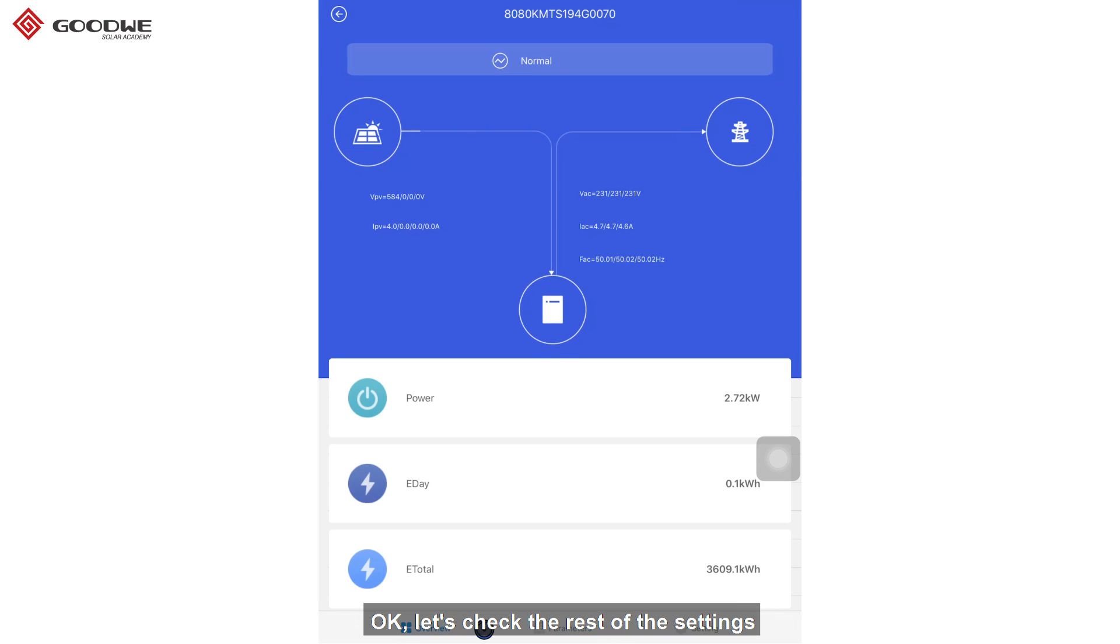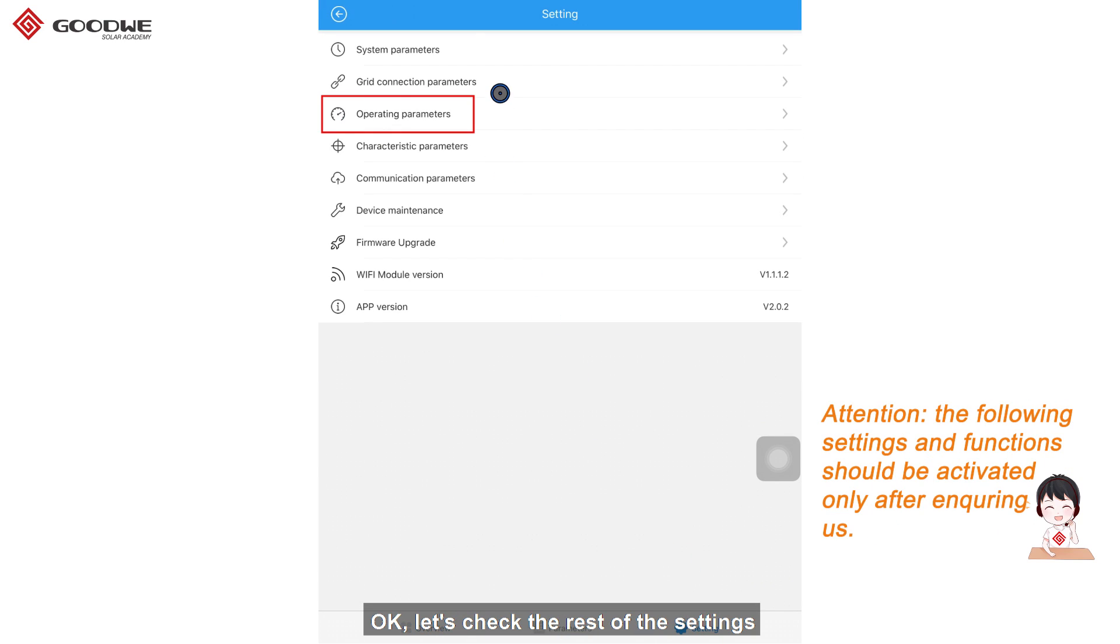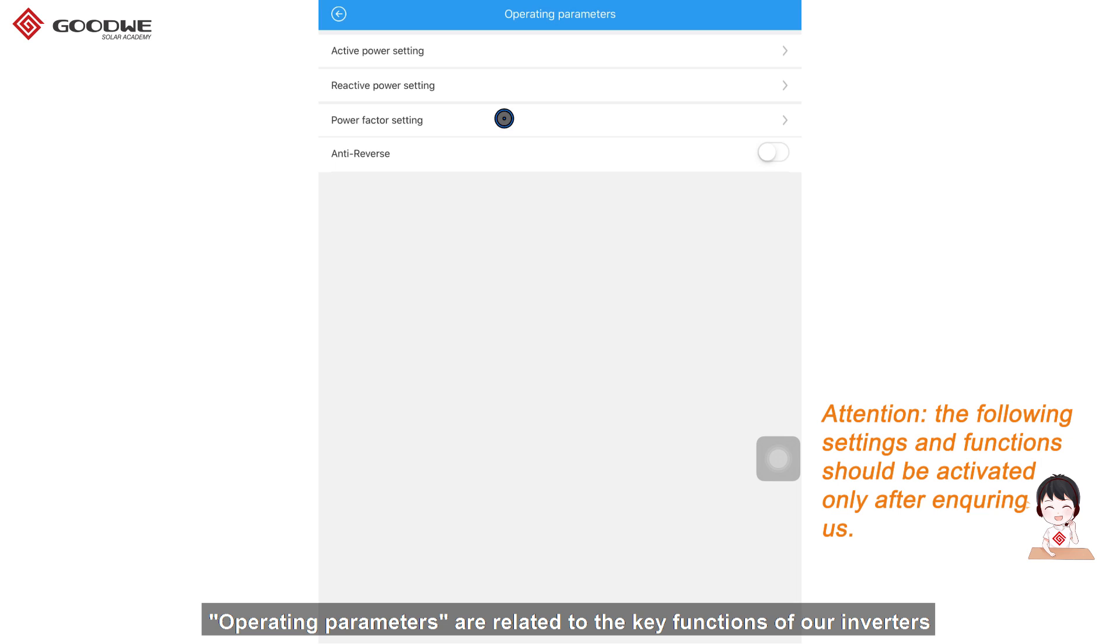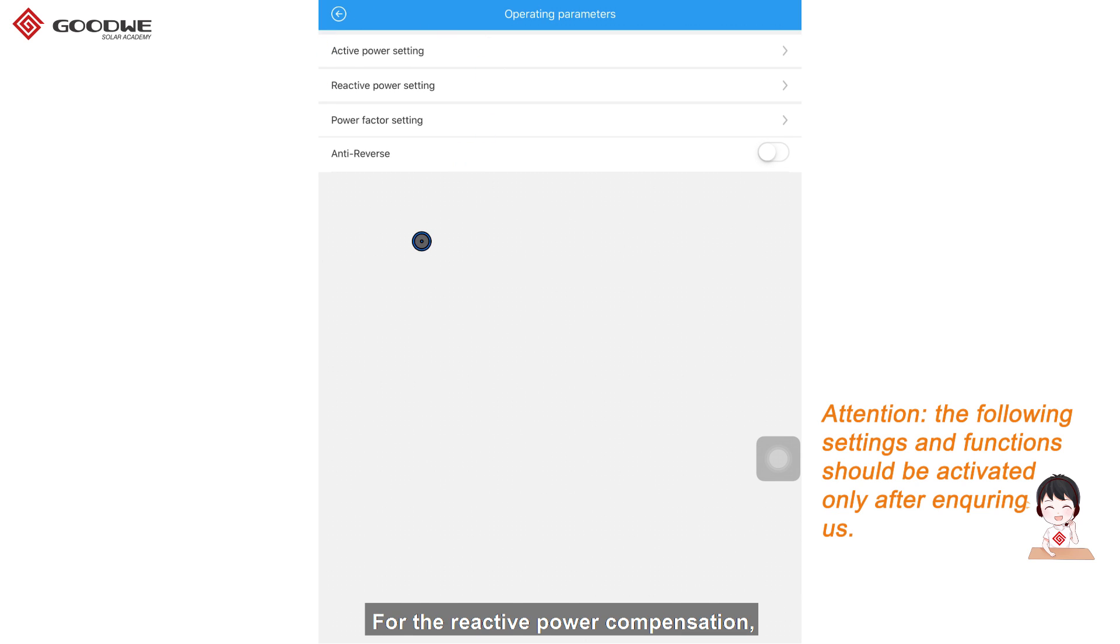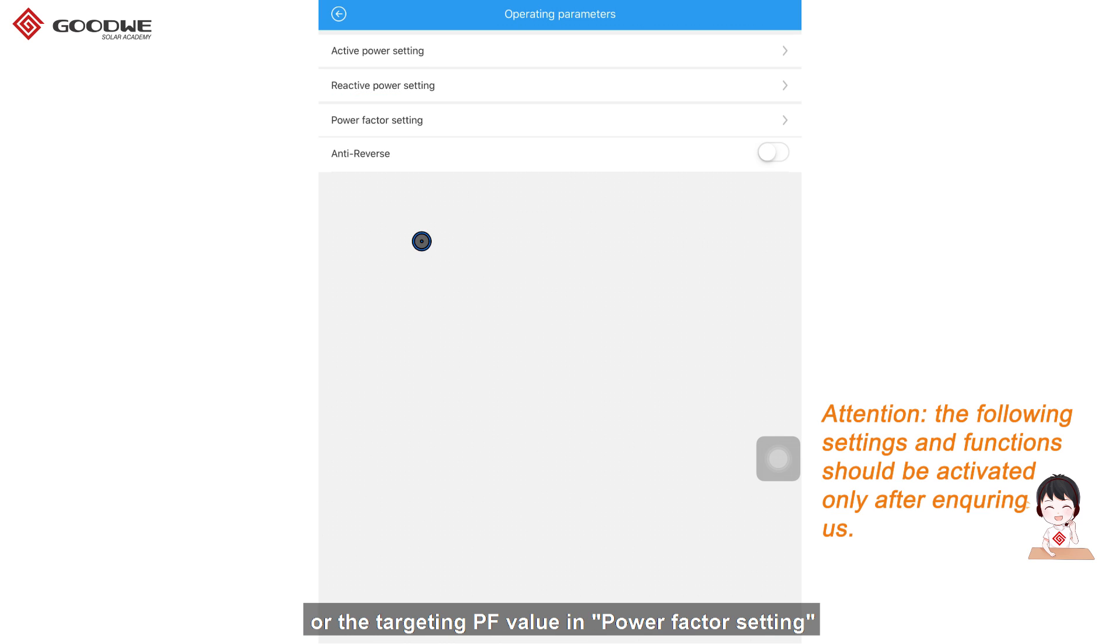OK, let's check the rest of the settings. Operating parameters are related to the key functions of our inverters, including reactive power compensation and power limit. For the reactive power compensation, you could set reactive power needed in reactive power setting or the targeting PF value in power factor setting.